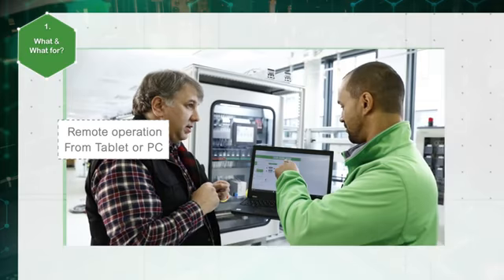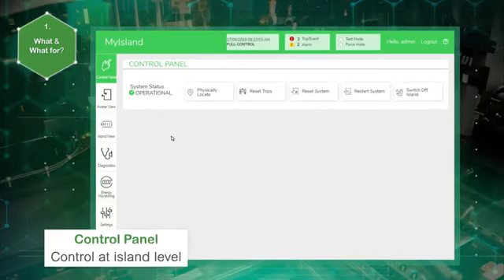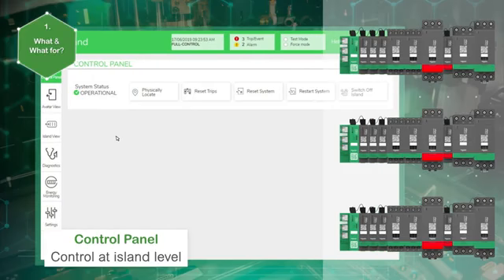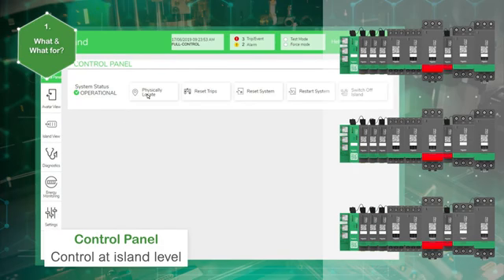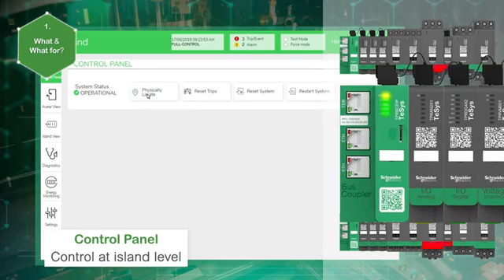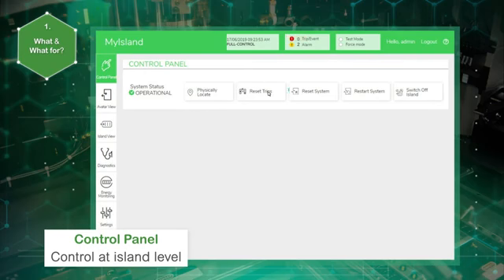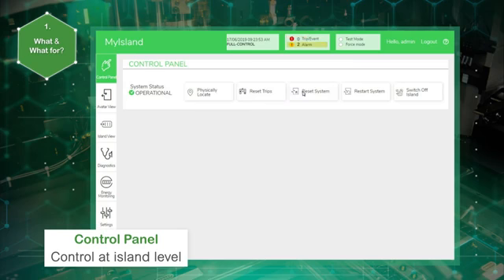The control panel gives access to most frequently used functions for controlling and managing the island. When multiple islands are in the same network, the locate island function helps verify that you are connected to the correct island. The bus coupler's power LED illuminates steady yellow for five seconds. It is possible to reset all the trips on the island, reset the system after a minor event occurs, restart the island, or switch off the island for maintenance purposes.